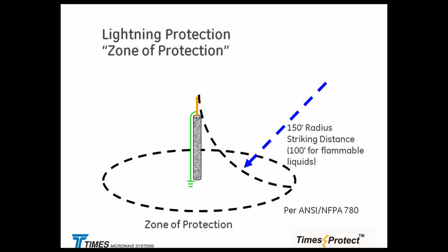And my question was always, so if you are running a green or green yellow or green insulated wire or bare copper wire on the side of the tower, is that Ben Franklin rod insulated and isolated electrically and mechanically from the tower? No, it isn't. It is just bolted right onto the tower. I say, well, so what's the purpose behind it? As I keep telling people, you know, does it help you? No. Does it hurt you? No. So if your local inspectors and so on believe in that whole thing, you know, let's leave it there to keep the peace and quiet.